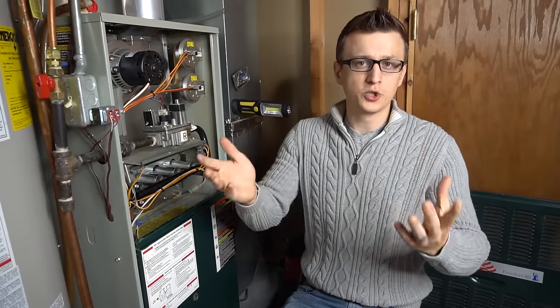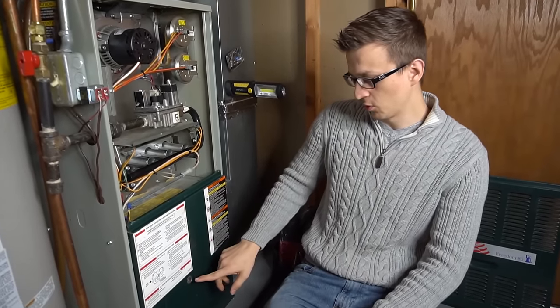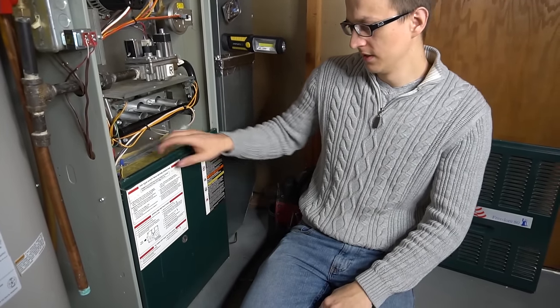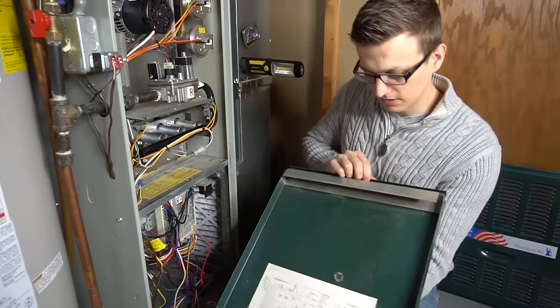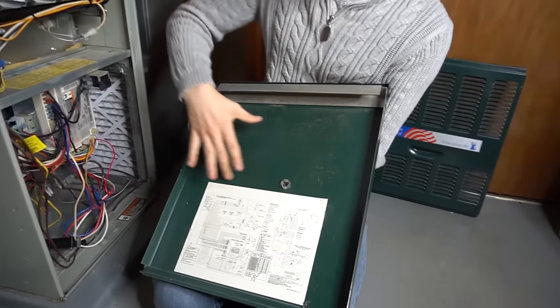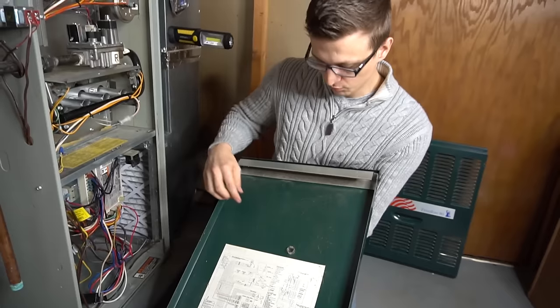Today I want to talk about a tripped rollout switch or flame rollout switch, which usually goes hand in hand with your control board blinking an error code. If you take your furnace door off, there will be a chart that explains the code blinking on your control board.